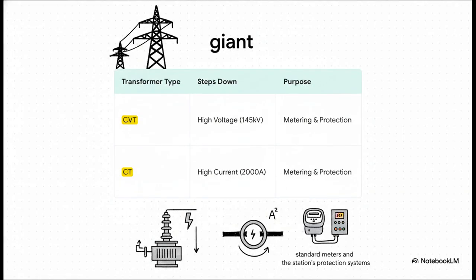You don't try to measure the giant, you measure its shadow. These special instrument transformers create small, safe, and perfectly proportional little copies of the voltage and current. So CVTs shrink down that massive voltage, and CTs reduce the huge current to tiny, manageable levels that all the standard meters and the station's own protection systems can handle safely.